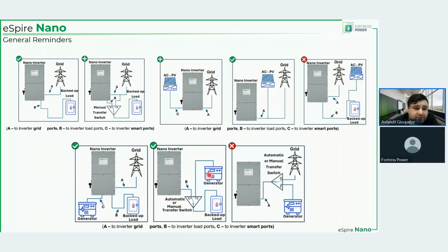I'm sorry, I drifted away. First of all, yes, you can do that, what I was just describing. It's just that a manual transfer switch would be introduced in this solution right here, and it would sit between the generator and the backup panel. Option number 2 is you have the load output of the inverter and the generator go to the emergency port of the automatic or even manual transfer switch.